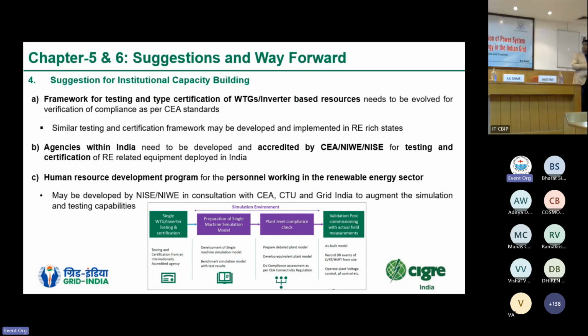Then for capacity building, this is really important since all these resources are inverter based, and the power system operation as well as the plant operation with these resources require in-depth knowledge and understanding of their performance. So complete institutional capacity building is required. Under that, certain points are important, like testing and type certification of WTGs and inverter-based resources for compliance of the CEA standards.